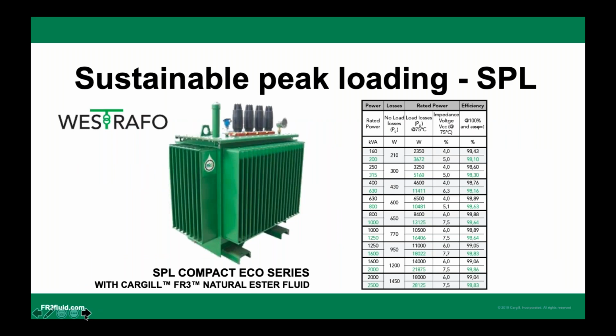One slide I would like to discuss here. This has been a modern practice now. If you carefully see this paper, what they are saying is that with this fluid transformer, you can use a 630 kVA transformer in place of 750, or a 400 kVA transformer in place of 630, and all the losses, impedance and efficiencies are given here. So by a slight compromise sometimes on efficiency, and only when you need it, it will give you a significant saving on the transformer's cost as well as the size and the installation. As simple as a 400 kVA transformer in place of a 630 kVA transformer. You can imagine how much savings you are making. Let's move on to the next.